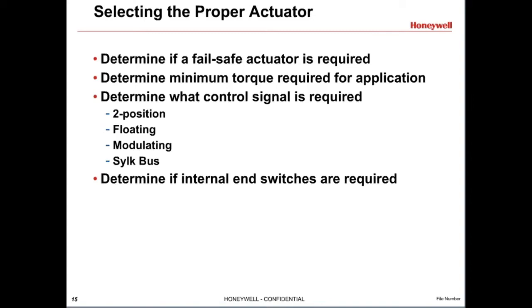Sylk Bus is a communicating control signal. This is a digital communication signal that uses a 2-wire bus to provide control and communications between a Sylk-enabled controller and a Sylk-enabled actuator. Honeywell DCAs also come with optional internal end switches. This is sometimes referred to as feedback. Be sure to select a model with end switches if feedback is needed.